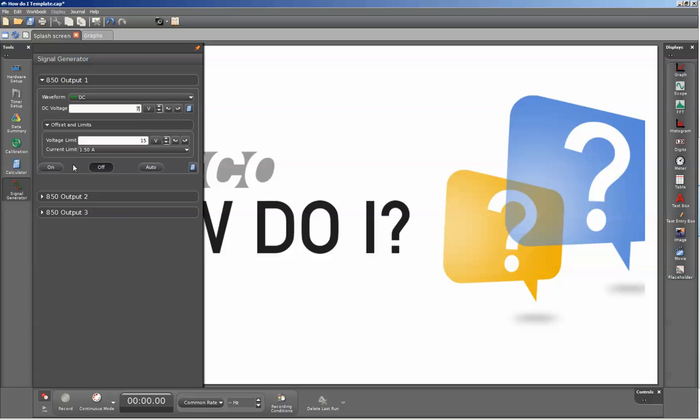The controls for the signal generator are below. On means that the signal generator is on all the time. Off means that the generator is off. And auto means that the signal generator will only turn on when you are actively collecting data.